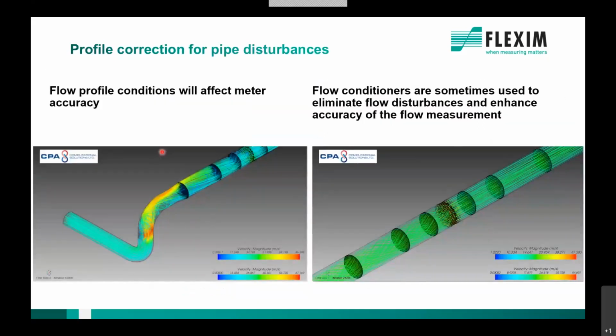So here are some examples of what flow profiles may look like. We have quite an extreme example. That's a double bend out of plane. Extreme because it causes a swirl as well, but not extreme in a way that we don't find it very often. That's quite a common flow profile disturbance we find in the field. That means after such a flow disturbance element, the double bend out of plane in that case, we have a swirl, and the turbulence, the disturbance, is in the fluid for quite a long time.